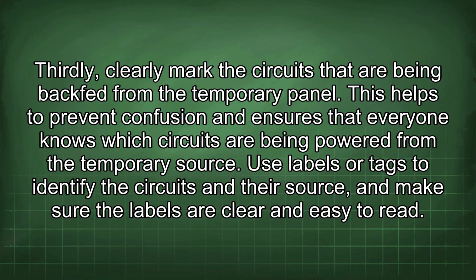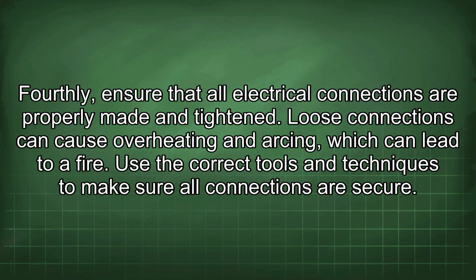Thirdly, clearly mark the circuits that are being backfed from the temporary panel. This helps to prevent confusion and ensures that everyone knows which circuits are being powered from the temporary source. Use labels or tags to identify the circuits and their source, and make sure the labels are clear and easy to read. Fourthly, ensure that all electrical connections are properly made and tightened. Loose connections can cause overheating and arcing, which can lead to a fire. Use the correct tools and techniques to make sure all connections are secure.